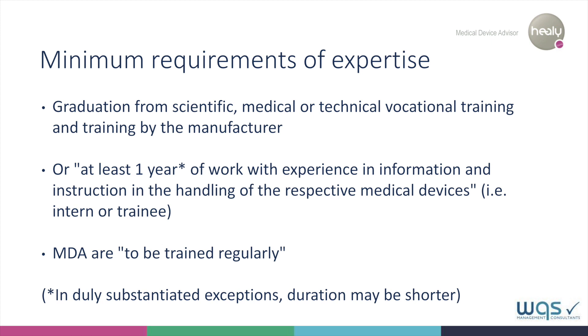Paragraph 31 of the German Medical Devices Act states that expertise only exists if the following conditions are met: the MDA has successfully completed training in a scientific, medical, or technical profession and has been trained in the relevant medical devices. Or, the MDA has gained experience with and information about the respective medical devices and, if necessary, the instruction regarding those devices through at least one year of professional activity. This time period may be shorter in some justified cases.